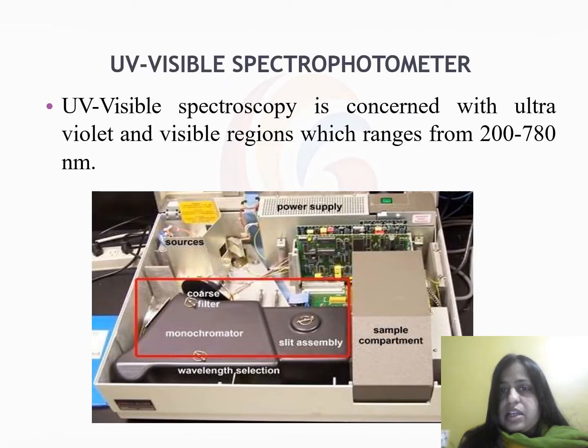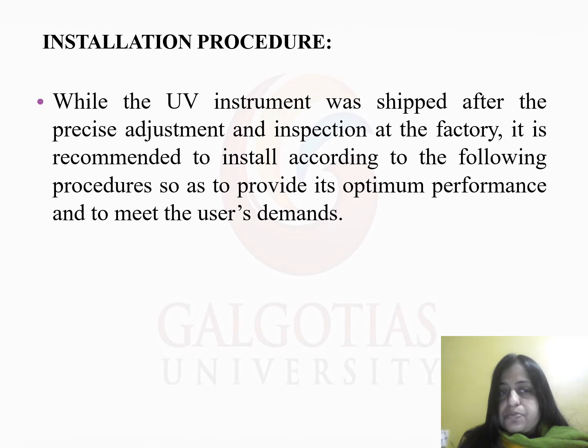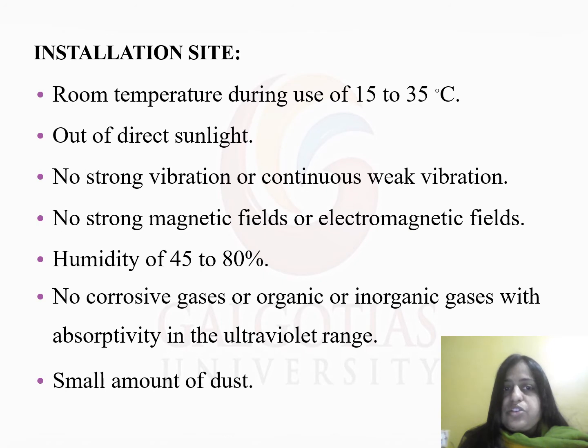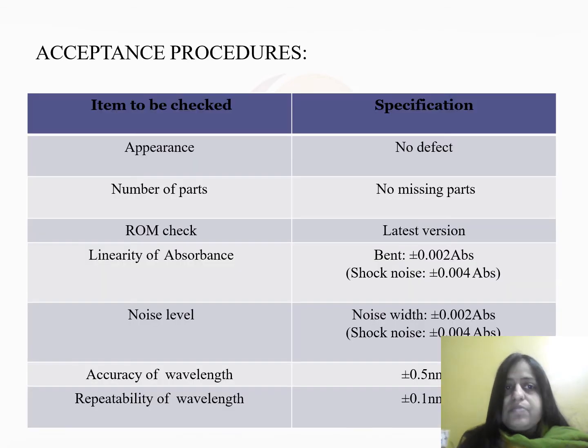The UV visible spectrophotometer is concerned with the ultraviolet and visible region, which ranges from 200 to 780 nanometer. Now the installation procedure. While the UV instrument was shipped after precise adjustment and inspection at the factory, it is recommended to install according to the following procedures so as to provide its optimum performance and to meet the user's demand. Installation site: room temperature during use of 15 to 35 degrees centigrade, out of direct sunlight, no strong vibration or continuous weak vibration, no strong magnetic field or electromagnetic fields, humidity of 45 to 80%, no corrosive gases or organic or inorganic gases that absorb in the ultraviolet range, and a small amount of dust.